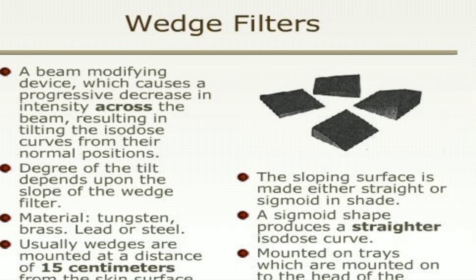Wedge filters cause a progressive decrease in intensity across the beam, resulting in tilting of the isodose curves from their normal position. The degree of tilt depends upon the slope of the wedge. Materials used to make wedge filters are tungsten, brass, lead, or steel. These are usually mounted at a distance of 15 cm from the skin surface. The sloping surface is either made straight or sigmoid in shape, as sigmoid shape produces straighter isodose curves. Wedge filters are mounted on trays attached to the head of the machine.